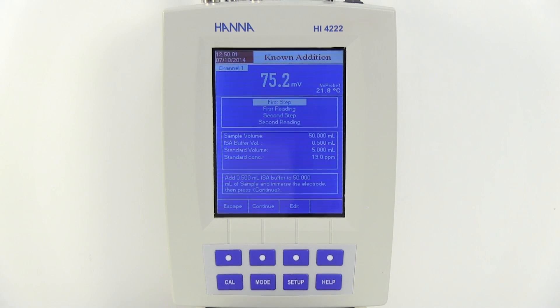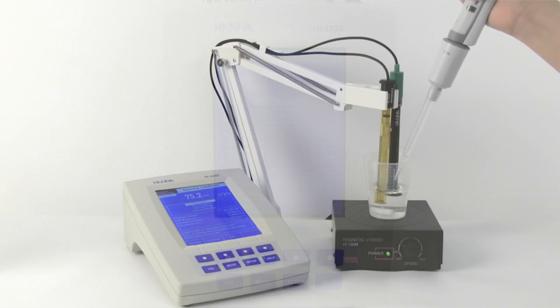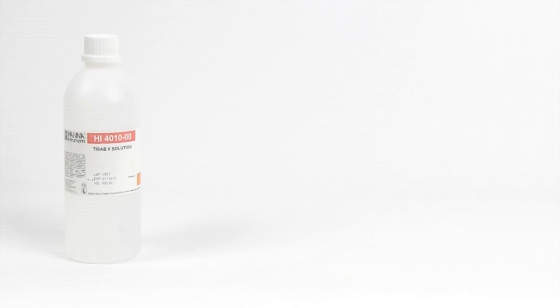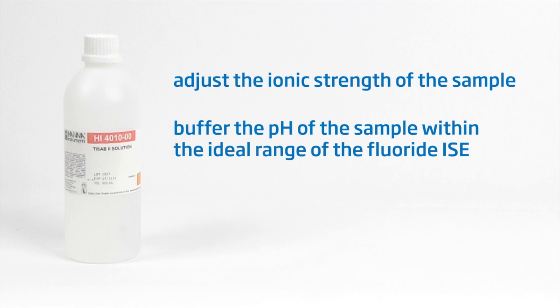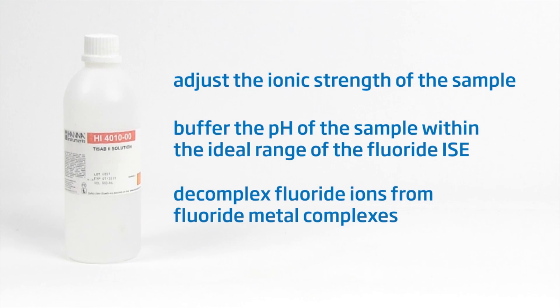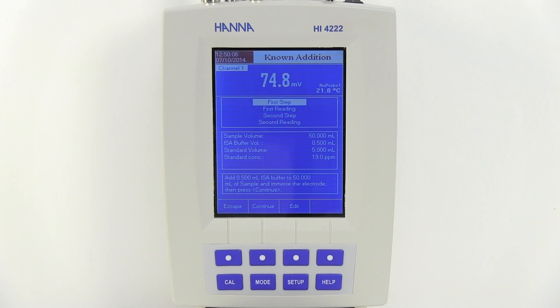Add 0.5 mils of HI4010-00 TISAB solution. The addition of TISAB to the samples serves three purposes: to adjust the ionic strength of the sample, to buffer the pH of the sample within the ideal range of the fluoride ISE, and to decomplex fluoride ions from fluoride metal complexes, ensuring they are free in solution and able to be measured. Once added, press Continue.